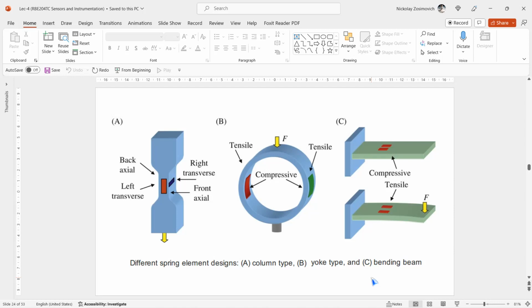This slide shows several designs of spring elements for the measurement of force for various ranges. On the left, figure A presents a typical construction for large load. The central part of the transducer, as you may see here, is a metal bar with reduced cross-sectional area where the gauges are mounted. The gauges are all shown in red. There are four strain gauges in a full bridge configuration. Two strain gauges, front and back side, measure the axial force, with equal sensitivity. And two other gauges measure the transverse force, also with equal sensitivity.